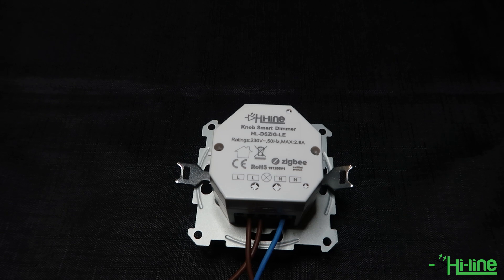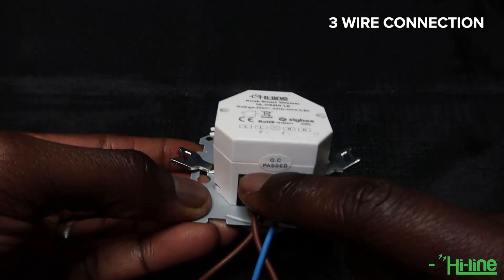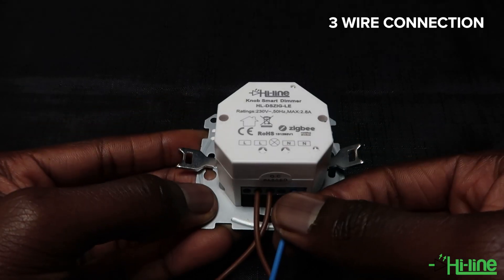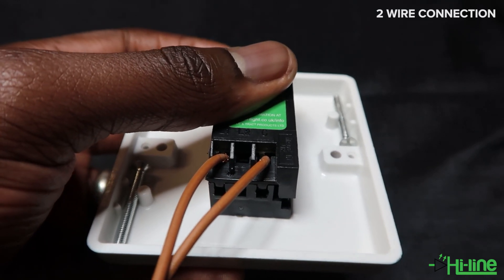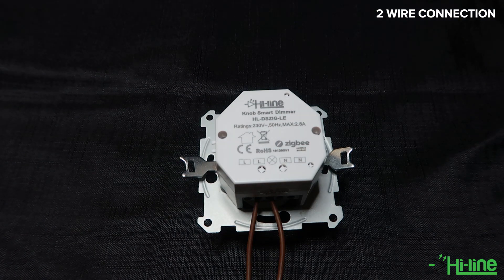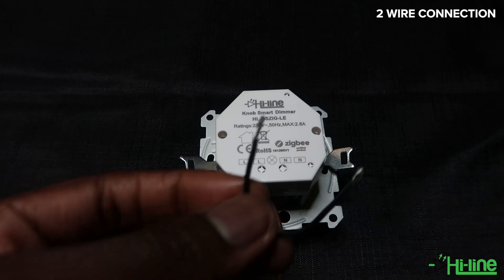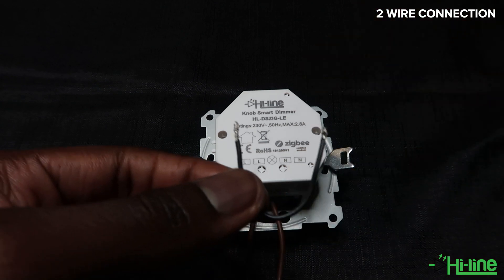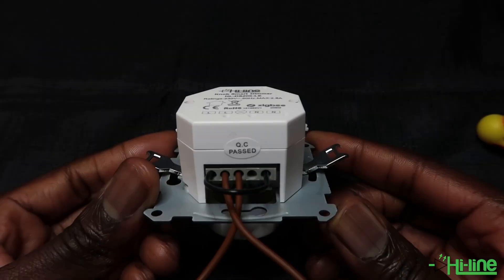For a three-wire connection you have your live input going in, your load output coming out, and your neutral cable. Most conventional dimmers use a two-wire connection — live in and load output. With the Knob smart dimmer, to have a two-wire connection you have to create a link between the live and the neutral. That way the inbuilt microprocessor can switch from a three-wire to a two-wire connection, and it will simply look like this.